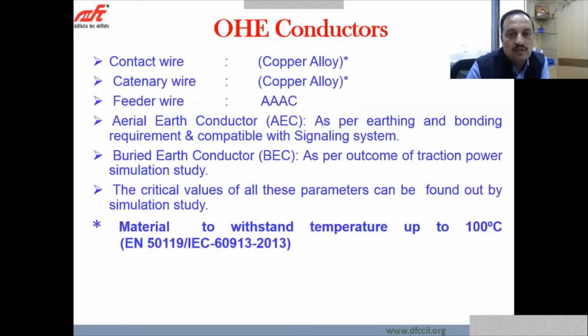Conductors: our contact wire is copper alloy, the catenary wire is also copper alloy, 150 and 125 square mm basically. The feeder wire is triple AC. The aerial earth conductor is as per the earthing and bonding requirement. The buried earth conductor has been designed, and the critical values of these parameters are based mainly on the simulation study. So the alloy used in the catenary and contact wire is mainly to withstand temperatures up to 100 degrees centigrade. So it also shows that we will be able to carry higher loads on our network, because the conductor sizes are larger and their temperature bearing capacity is also up to 100 degrees against the normal temperature of 50 degrees Celsius.